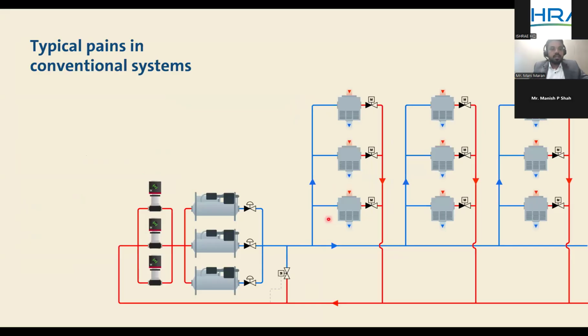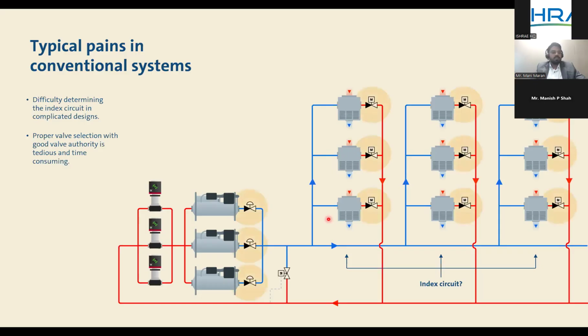So let's summarize the challenges that we can see in a conventional system. Though it does its job, we can still improve the efficiency to achieve the performance that we are getting today. The pain points are, first, difficulty in determining the index circuit. As I said, what is the critical load? Where is the critical load? What is the differential pressure that we need to set to modulate the flow based on changing demand? This is always a critical thing that we see in a variable primary system or a conventional variable secondary system as well.